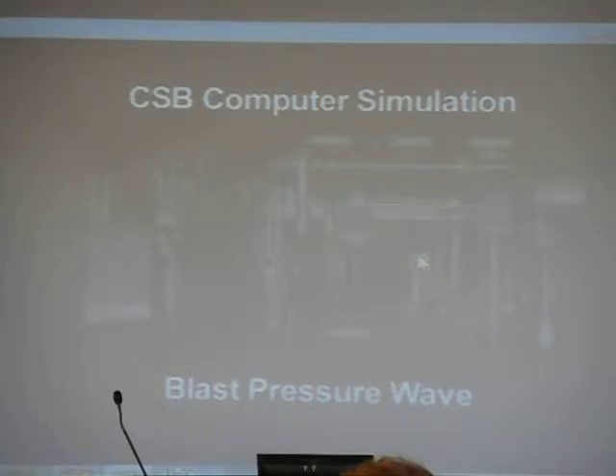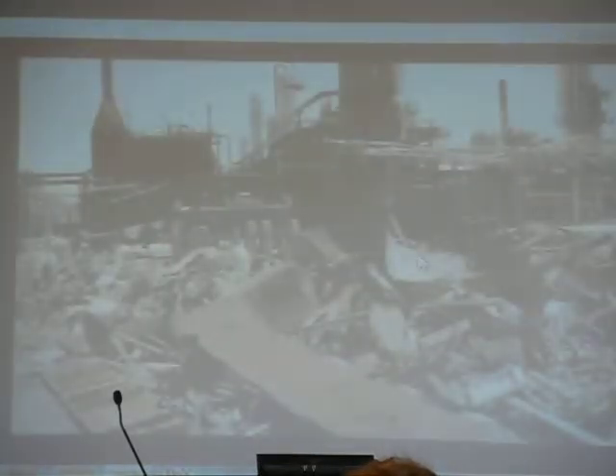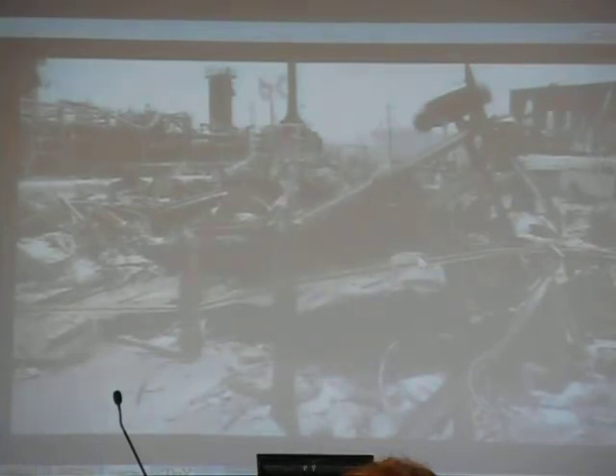A computer simulation shows how the blast pressure wave moved after the cloud was ignited — accelerating through the ISOM unit, causing heavy destruction and igniting more fires. This is the area where two trailers were destroyed, fatally injuring 15 contract workers. Videotape shot by Houston station KHOU shows the ISOM unit as fires continue to burn after the explosion. You can see the blow-down stack still emitting flames as hydrocarbons are released. Several vehicles were set on fire, over 50 large chemical storage tanks were damaged, and firefighters struggled to rescue the injured. The Chemical Safety Board's investigation to determine the root causes of the tragedy began the following day.